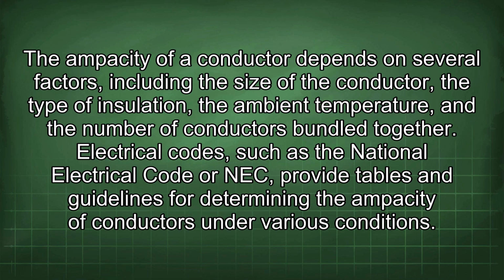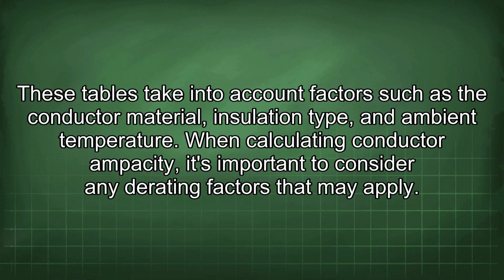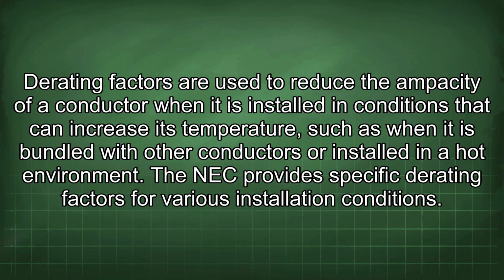Electrical codes, such as the National Electrical Code or NEC, provide tables and guidelines for determining the ampacity of conductors under various conditions. These tables take into account factors such as the conductor material, insulation type, and ambient temperature. When calculating conductor ampacity, it's important to consider any derating factors that may apply. Derating factors are used to reduce the ampacity of a conductor when it is installed in conditions that can increase its temperature, such as when it is bundled with other conductors or installed in a hot environment. The NEC provides specific derating factors for various installation conditions.